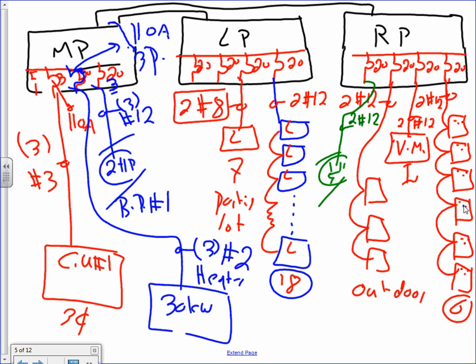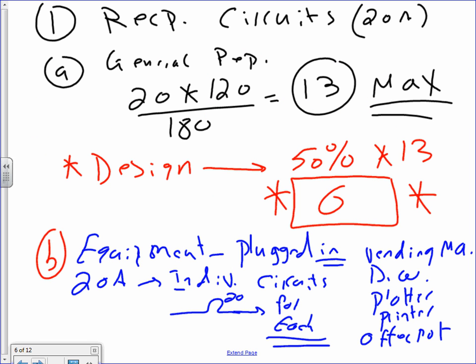We know how to size the feeder and the service. You guys know, because you did it for me. Now we're going to go down to the branch circuits and size them. Cool? Can you guys remember just the 6 receptacles and the 18 and the dedicated circuits for these numbers that we throw here? Remember them when you start circuiting later on. You're going to have the slide here with you. Okay, let's go and verify what Chad has done. Let me tell you what my verification is. And again, take it to your boss, and they might tell you that guy's a knucklehead. No problem. It wouldn't be the first.